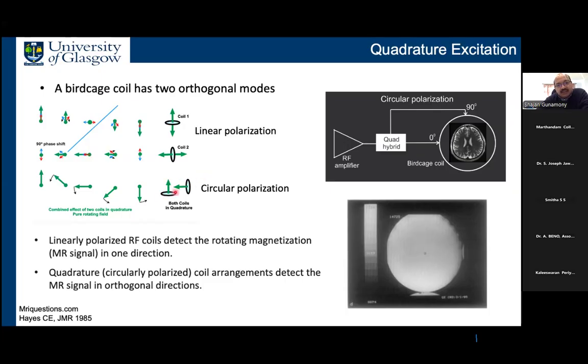If you have these 2 coils operating together, that means we have these 2 coils in orthogonal directions next to each other, then we pick up the signal from 2 orthogonal directions, or we excite the signal in 2 directions. So this is called circular polarization. I'm always talking about excitation and reception because it's also about transmit and receive, and they are always reciprocal. So the block diagram on the right shows the setup that we require to set up this kind of circular polarization. So in an MRI scanner, you have an amplifier which produces a very high RF power.